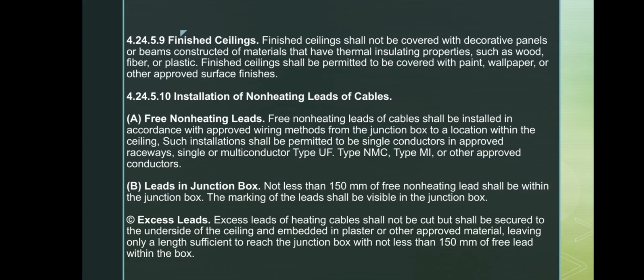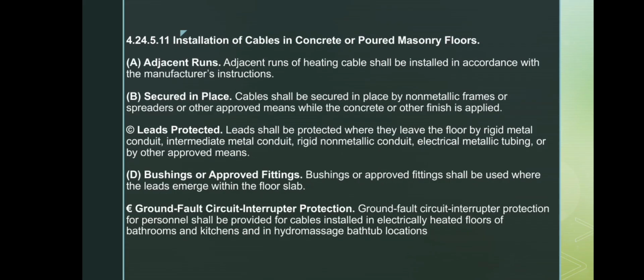Any excess non-heating lead must not be cut. Instead, it should be secured to the ceiling and embedded in plaster, leaving only enough length to reach the junction box with the required 150 millimeter of free lead. In this slide, we tackle the installation of cables in concrete or poured masonry floors.